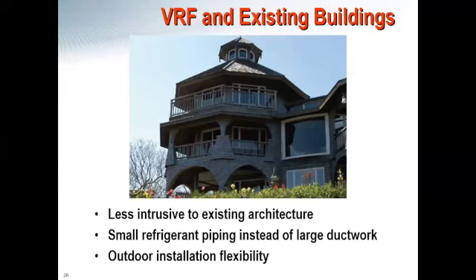One of the main advantages with VRF is that you're able to skirt around this because of how flexible the installation is. In most cases, we're going to be running small refrigerant piping instead of large ductwork to the space. We're going to touch on that in a couple minutes, to see exactly the difference between the piping and the ductwork.